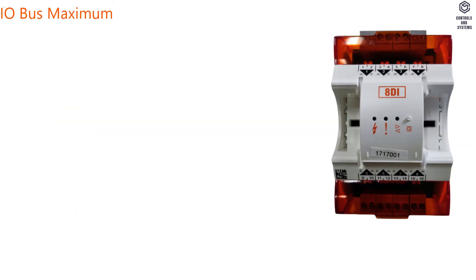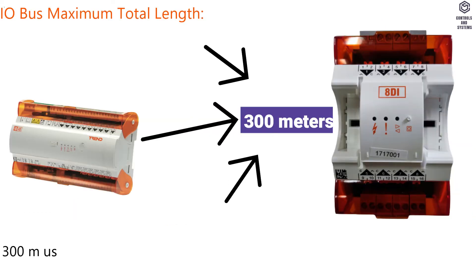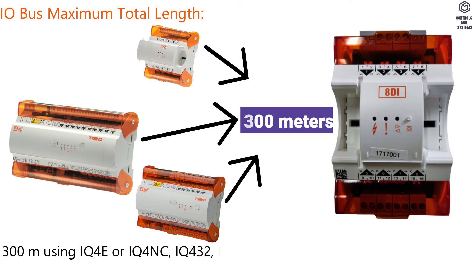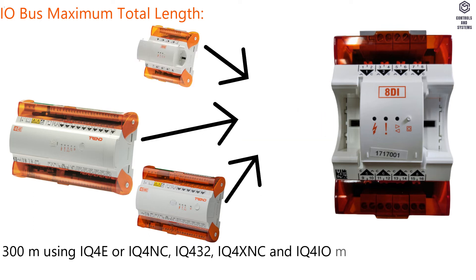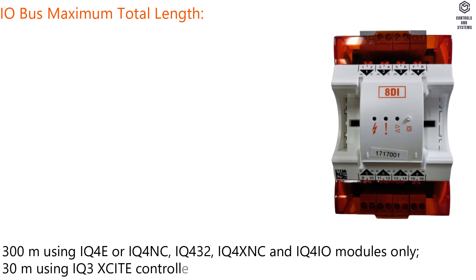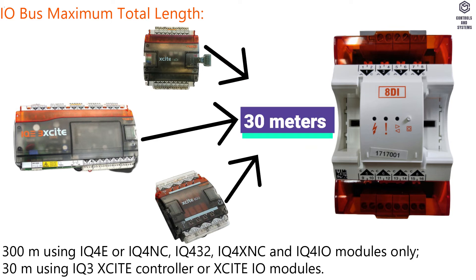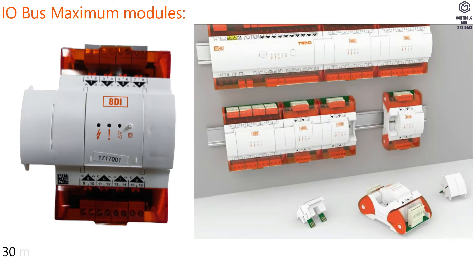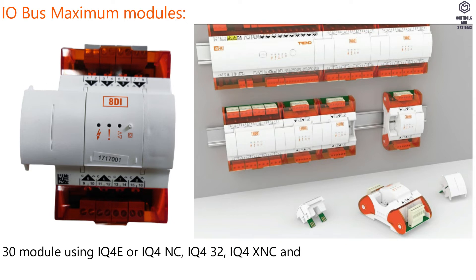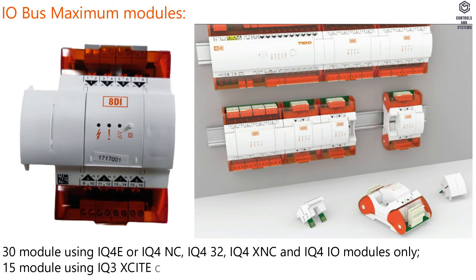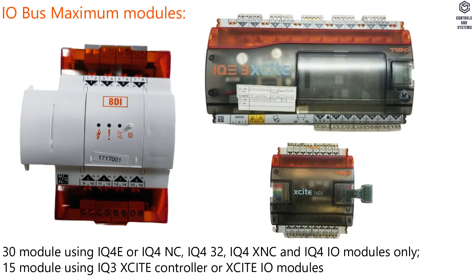I/O bus maximum total length: 300 meters using IQ4E or IQ4IO modules only; 30 meters using an IQ3 XCITE controller or XCITE I/O modules. I/O bus maximum modules: 30 modules using IQ4E, IQ4NC, IQ432, IQ4XNC, and IQ4IO modules only; 15 modules using an IQ3 XCITE controller or XCITE I/O modules.